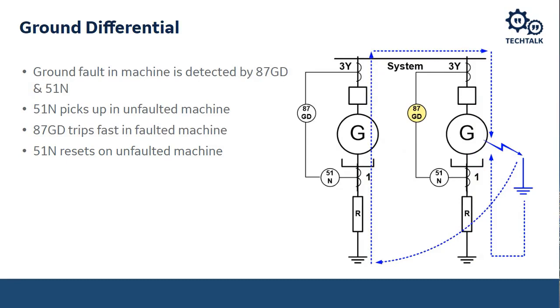For ground faults, a ground fault in the machine is detected by an 87GD. So if you have ground fault detection, it's the same as having the 67, where the ground differential protection will be able to follow exactly which machine the fault is on and only trip that particular machine, allowing the 51N to reset and not trip both machines.